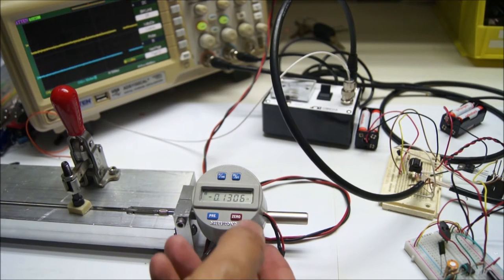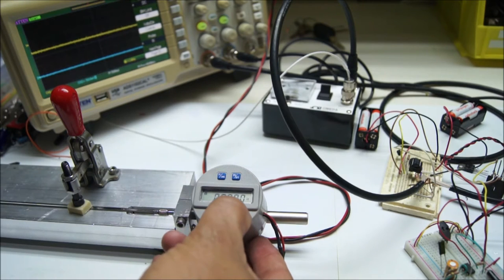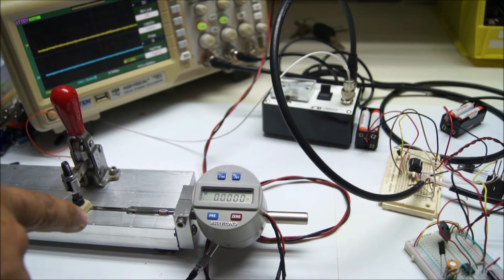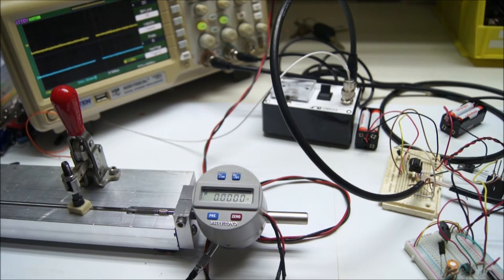So it's in. First thing we do is zero the indicator. That tells us where the cannula is, and the anvil has a step in it that's 50 thousandths away from, or inside the cannula.